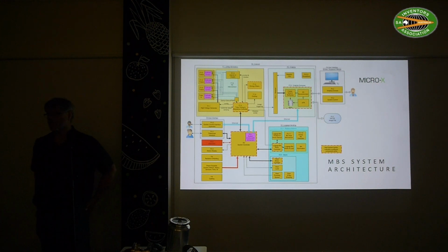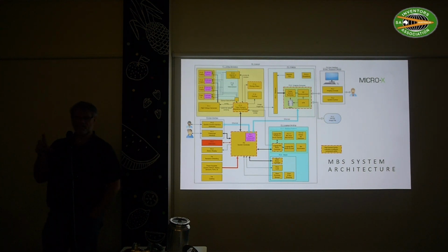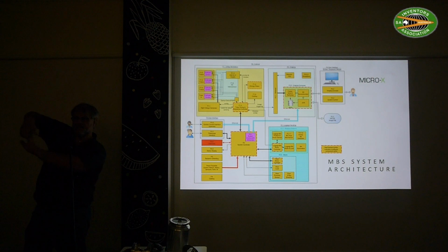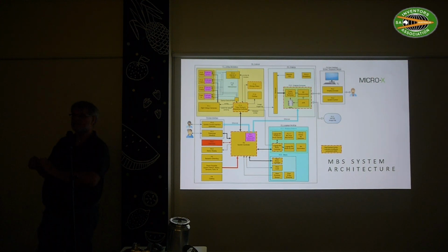Faraday cage can't shield it enough? A Faraday cage is electrical, but in a lot of ways the same principle applies. In Faraday cages, if the openings are close enough for the frequency you're trying to block, you can have a door with fingers rubbing on the edge, and you can have an opening underneath. For X-ray, that opening underneath will go straight through. So you need a door pull on the other end that folds over, and then the door closes like this. You get enough bounces for the X-ray, because every time it bounces, it loses energy, to the point where it finally comes out with so little energy that it's no longer a problem. That's the trick. But with moving doors, that is all very tricky.